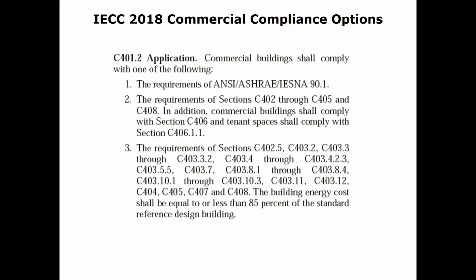You have three ways that you're allowed to comply with the code. You can either throw the code book in the trash and instead follow ASHRAE 90.1 2016 version in its entirety, or you can follow the international code in its entirety, one or the other. What you cannot do is cherry pick some things from one and cherry pick things from the other. You either go into this book or you go into that book. And if you follow 90.1, then IECC says that's good enough. You followed enough things that we're good with that.